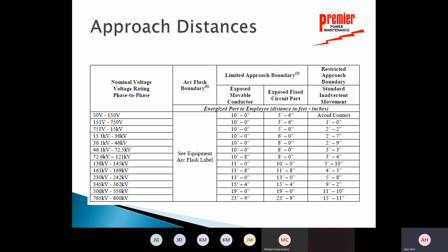So a couple charts here, and then we'll be done. But nominal voltage level. They came up with the chart, and this is directly out of NFPA 70E, and I only did the qualified person, but limited approach boundary, that's the unqualified person, and restricted approach boundaries for the qualified. So basically, the area you're going to be working most of the time is 150 volts to 750 volts. If it's movable conductor or moving wire, for unqualified person, it'd be 10 feet, typically be 3 foot 6 inches. For you, the qualified person, it would be 1 foot. 751 up to 15 kV, I'll do the qualified only, it says 2 foot 2 inches.